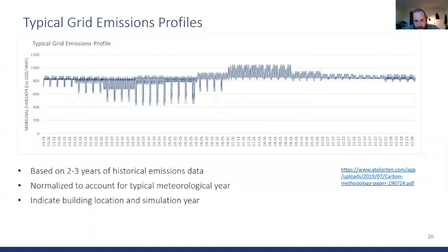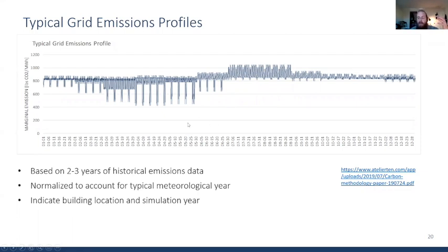We started thinking about how to approach this from a building design standpoint. Here's a random building with meter data showing electricity consumption and corresponding emissions — they don't really talk to each other. What tools do designers need to think about carbon in a more time-differentiated way? We've created what we call TCY — Typical Carbon Years — where we take three years of historical data, average it by weekday/weekend and hour by month, so you can see trends like spring curtailment and midday summer dirtiness. You send us your location, latitude/longitude, and simulation year, and we rearrange weekends, weekdays, and holidays and return an 8760-hour file you can compare to your energy model.